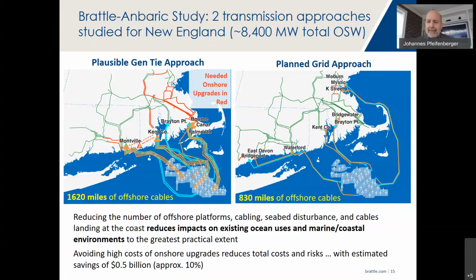Just knowing that these savings exist might help you get there, by making individual procurements sizable enough to support HVDC solutions, and then maybe doing a procurement where you pay more for the delivered power but get it into parts of the grid like the Boston area that later avoid expensive onshore upgrades. What we found is that despite spending about $2 billion more on the offshore HVDC lines, which are more expensive, you more than make up for it by reducing the onshore upgrades, with cost savings of about $500 million compared to the alternative.